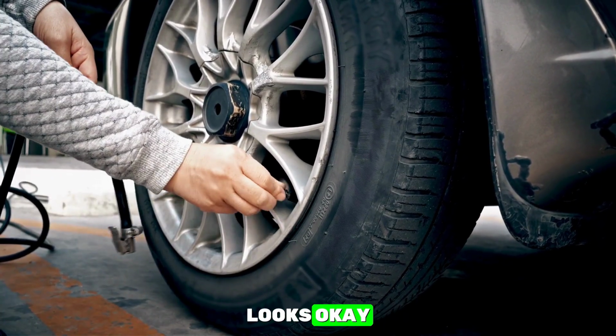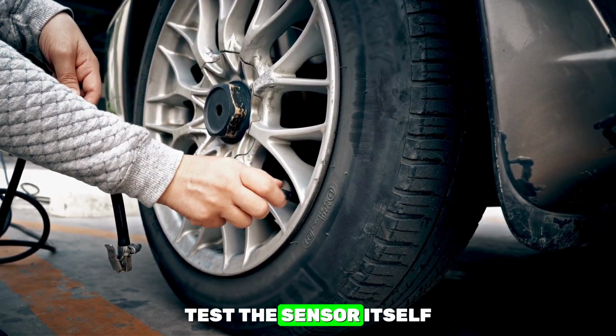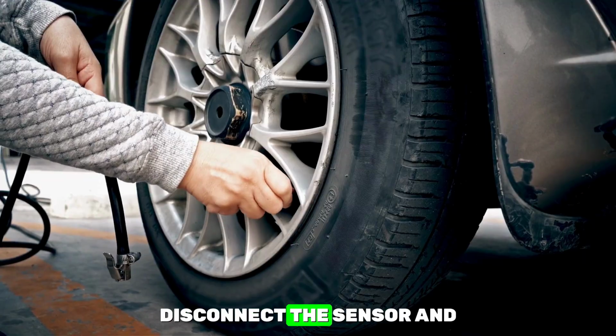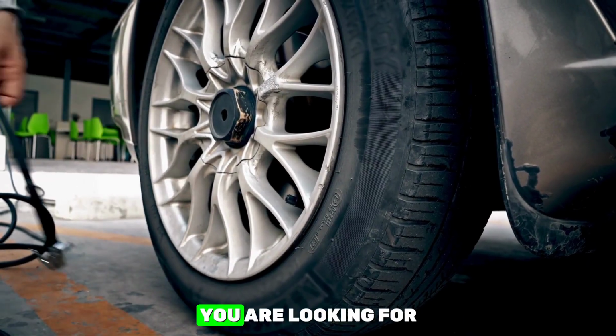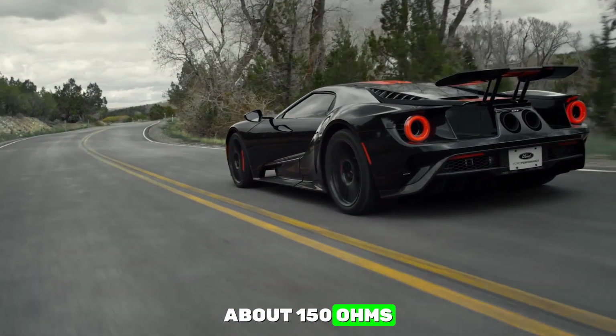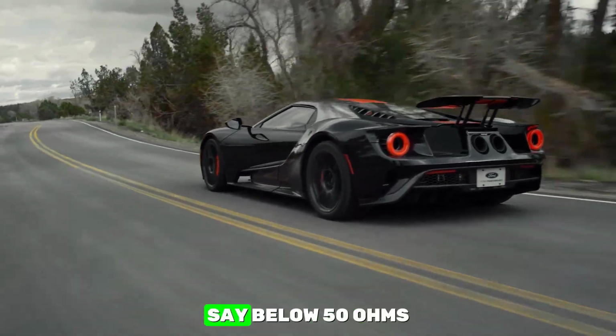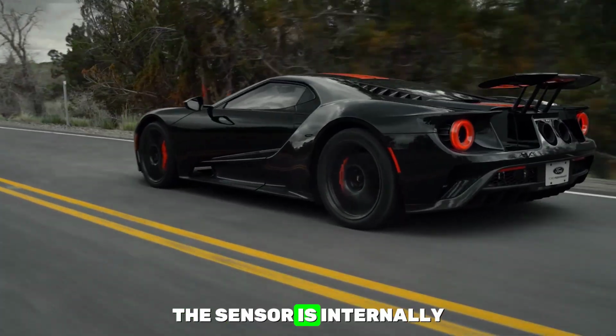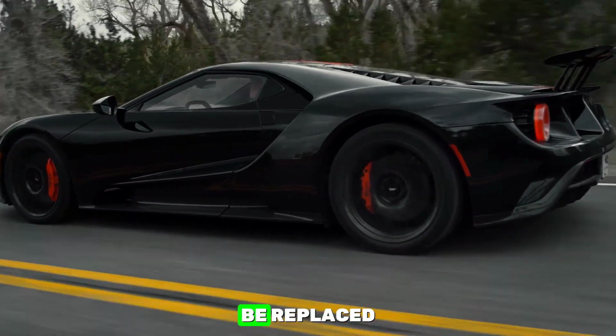If the wiring looks okay, you will want to test the sensor itself with an ohmmeter. Disconnect the sensor and probe the 2 terminals. You are looking for about 150 ohms. If the resistance is very low, say below 50 ohms, the sensor is internally shorted and needs to be replaced.